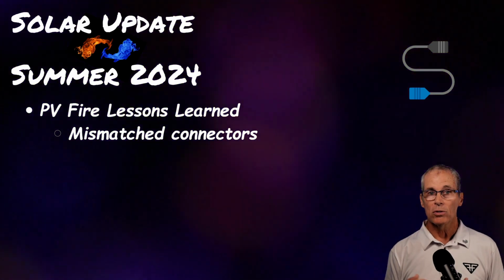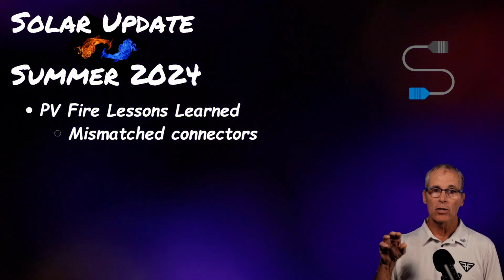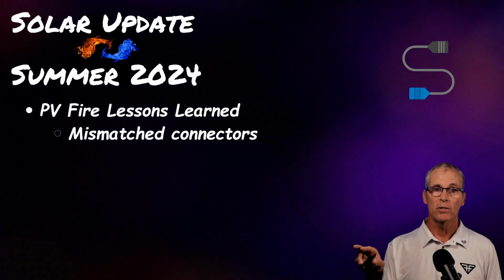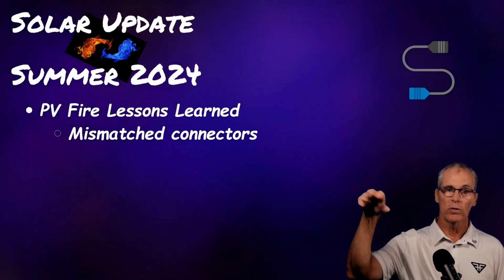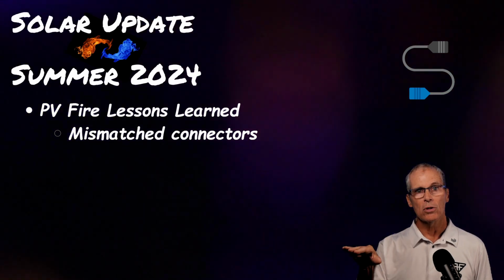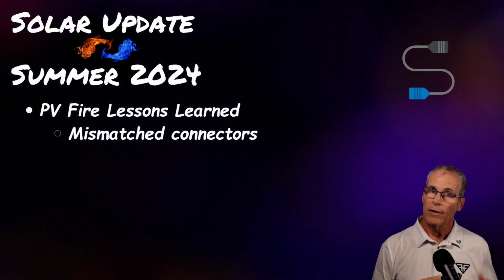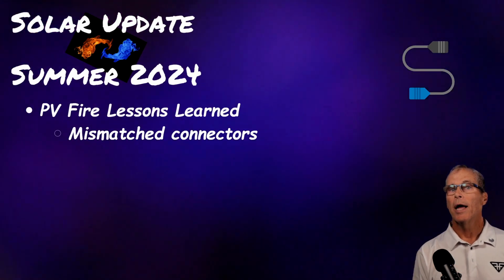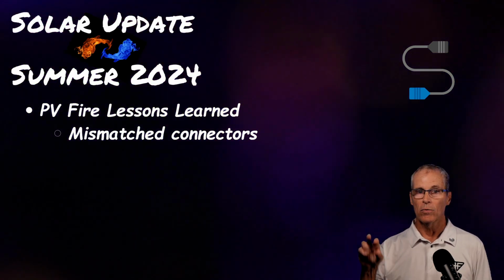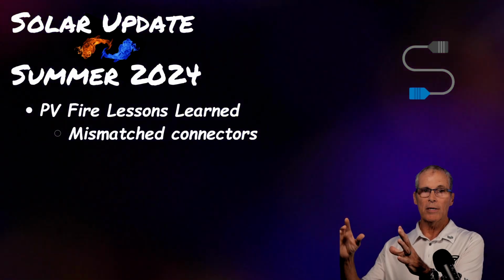And my view is that we need to keep an eye on them. So having some sort of thermography in place that can see underneath the panels, not just above the panels like a drone would see, but get under the panels to look at the connectors, that would be a proactive approach. And having some spares which had matched connectors ready to go, and then have a plan that, after we discover the first mismatched connector, we're going to start inspecting the connectors.